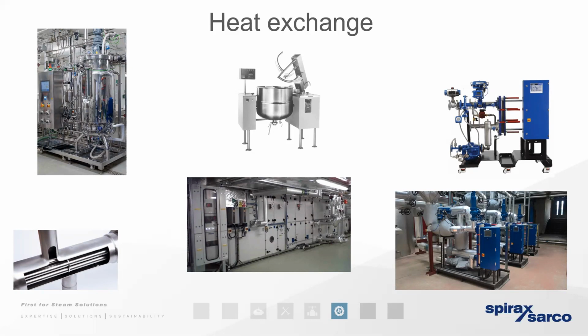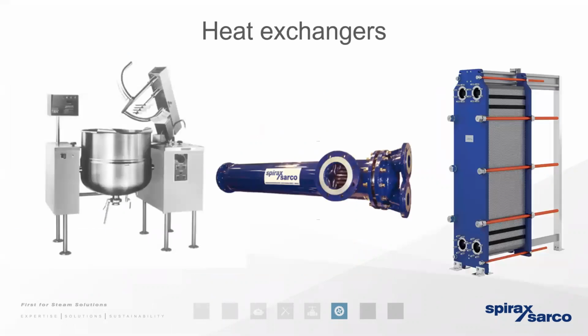And it bears mentioning that steam can be used for direct injection processes, commonly used in the food, beverage, pharmaceutical, and healthcare sectors, for example. But if we're using steam for direct injection processes, then that steam and also the condensate itself becomes absorbed into the atmosphere. For example, if we're using steam for humidification, there isn't any condensate to remove because it becomes part of the atmosphere. So under these circumstances, it's the latent heat and the sensible heat that go into the process. But for the vast majority of applications, we look at removing condensate from typical closed loop systems.